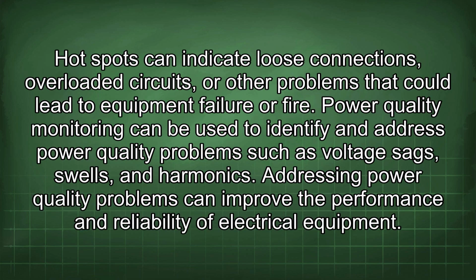Hot spots can indicate loose connections, overloaded circuits, or other problems that could lead to equipment failure or fire. Power quality monitoring can be used to identify and address power quality problems such as voltage sags, swells, and harmonics. Addressing power quality problems can improve the performance and reliability of electrical equipment.